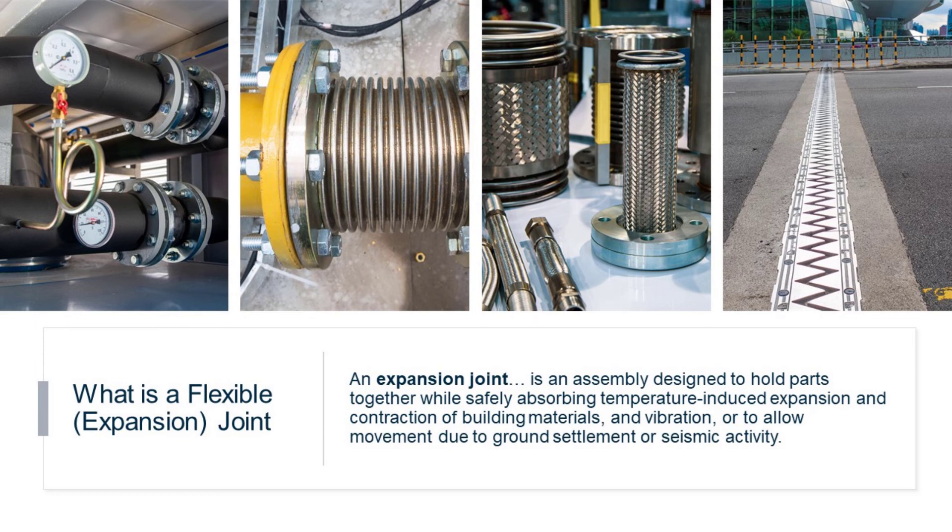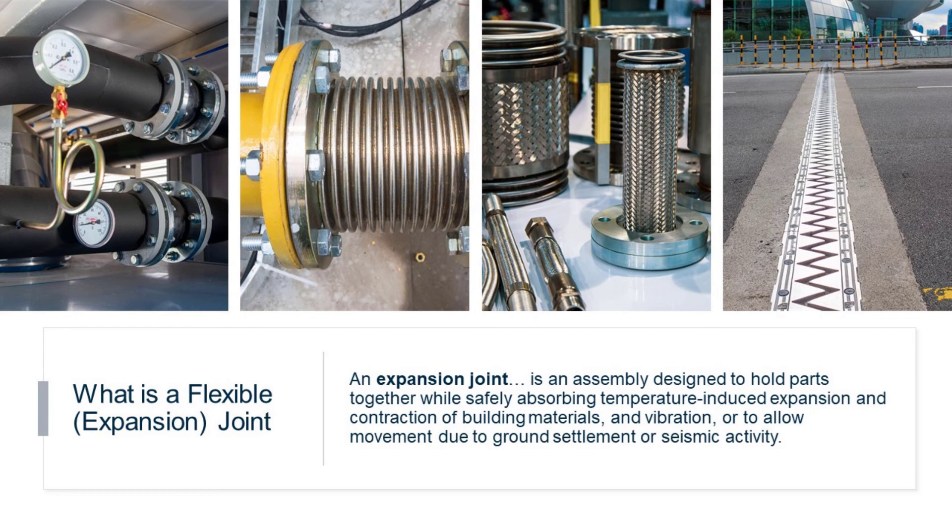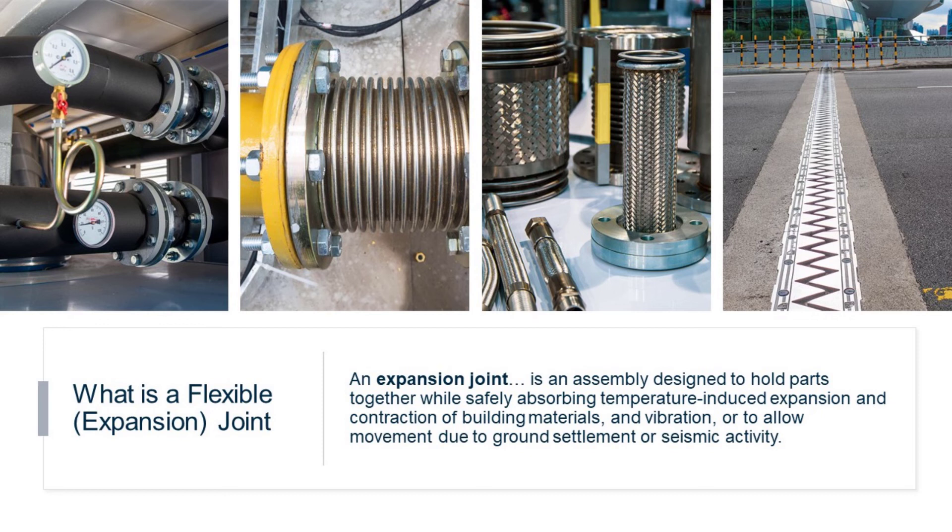Pipe expansion joints can be made of metal, plastic, fabric, or rubber, but we will be focusing on metallic expansion joints here today. Expansion joints are commonly used in areas with limited space. A hard pipe expansion loop would be able to absorb the thermal expansion to alleviate the stresses due to high temperatures and would commonly be the first option, arguably the first option if possible, because hard pipe is more economical in the long run and requires less maintenance.